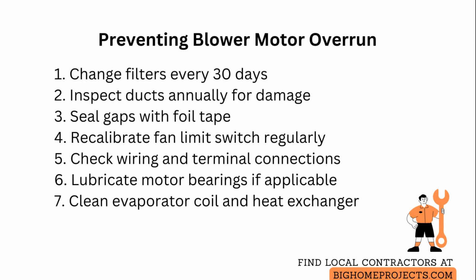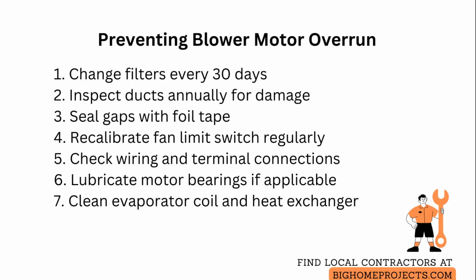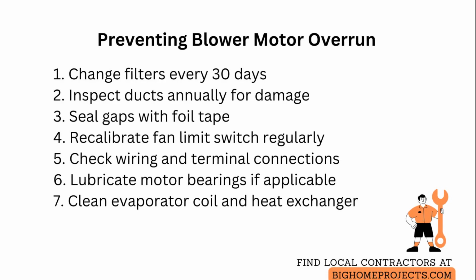Check all control wiring and terminal connections for corrosion, loose screws, or frayed insulation at least once a year. A secure 5-second wiggle test on each connection while power is off helps reveal hidden problems.